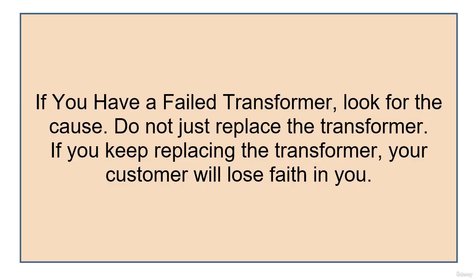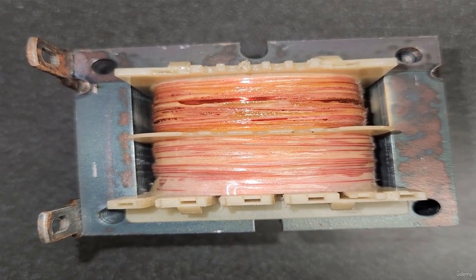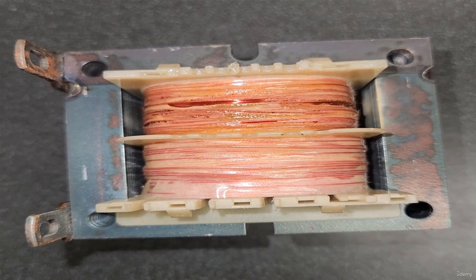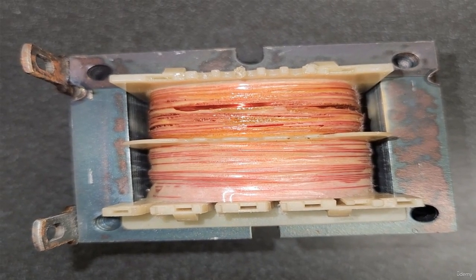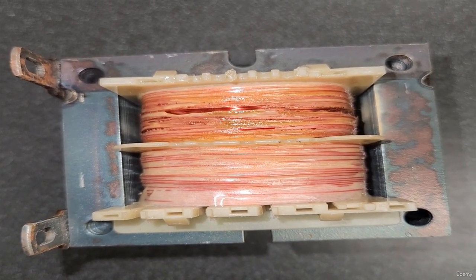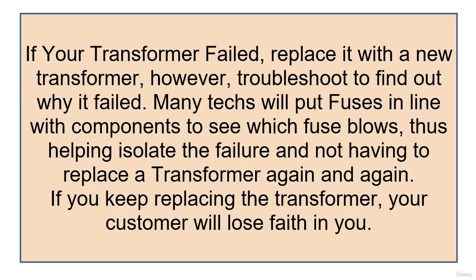If you have a failed transformer, look for the cause. The problem was not in the transformer. The only other reason a transformer would fail is exposure to high heat that melted the winding insulation, causing it to short to the iron core. If your transformer failed, replace it with a new transformer. However, troubleshoot to find out why it failed.